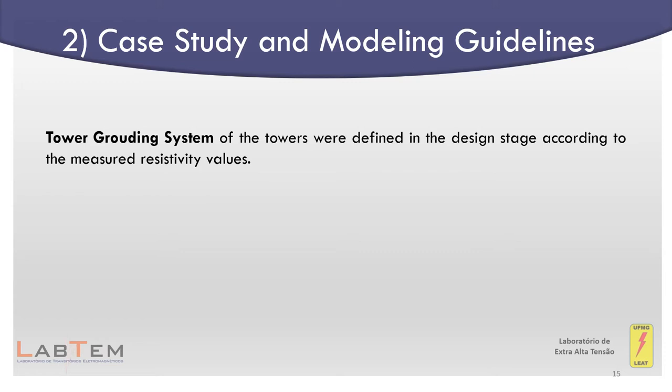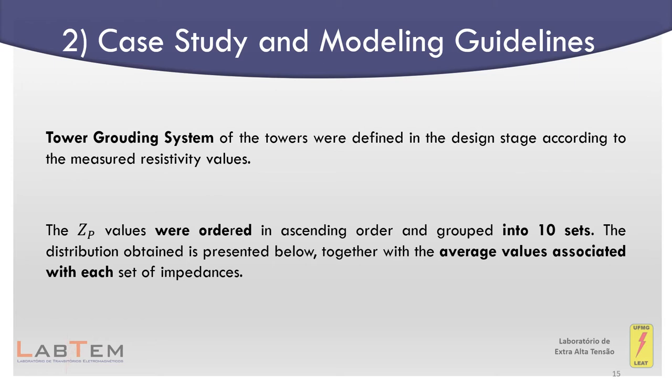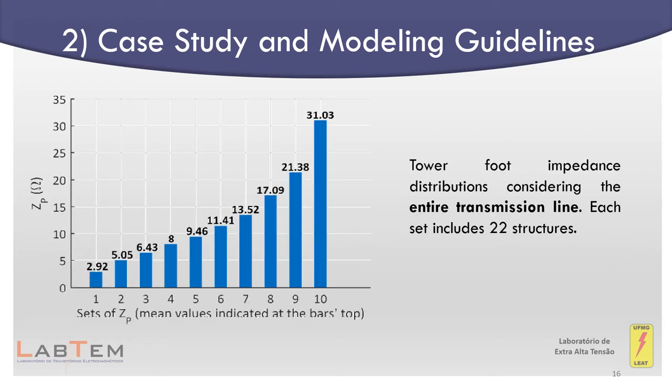The tower ground systems were defined in the design stage according to the measured resistivity values. The low-frequency ground resistances were calculated from the effective tower perimeter for each configuration. Impulse impedances were then estimated using the impulse coefficient. The impulse impedance values were ordered in ascending order and grouped into 10 sets. The distribution obtained is presented, together with the average values associated with each set, and this is used in the conventional methodology detailed in the next section.